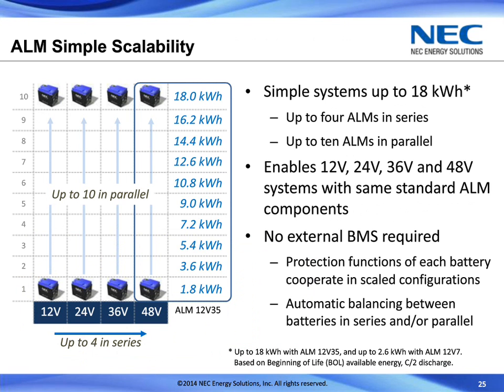In addition to the performance and so forth, is our ability to scale these batteries without having to do any external battery management system. These batteries can be configured into series configurations, so we can take a 12-volt battery, put them in series to get 24 or 36 or 48-volt configurations, and then we can scale them in parallel up to 10 batteries deep to create battery systems that can range up to 18 kilowatt hours of capacity at 48 volts. This really covers a wide range of different potential applications, and we don't require an external BMS to do this. We provide all the protection functions that are required for lithium-ion batteries in this configuration, as well as automatic balancing of capacity between the different batteries within those strings. So it's a very flexible and very easy to use battery system that's quite scalable, even though the initial capacity is 35 amp hours.